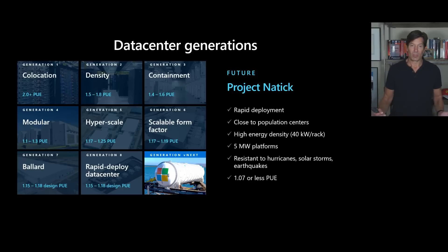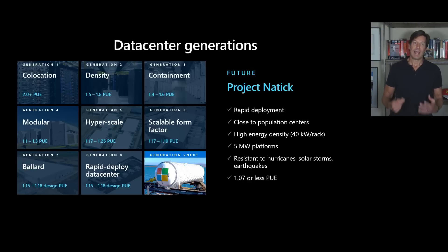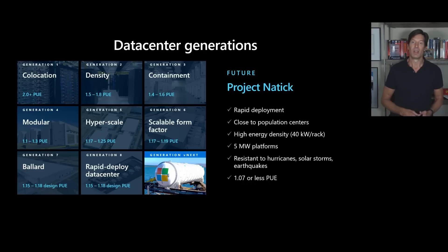First, the majority of the world's population centers are near a coastline, meaning we can deploy underwater data centers and serve just about all of the world very efficiently. Because they're on the ocean floor, they take advantage of ambient water temperature to cool, driving PUEs to levels we couldn't achieve in land-based data centers. They're also resistant to hurricanes, solar storms, and earthquakes. We can deploy them extremely quickly — you're looking at Natick V2, where we took 12 racks of Azure servers, put them in the cylinder, and dropped them a kilometer off the coast of Scotland in about 100 feet of water. From the time the cylinder was made to the time servers were on the ocean floor powered on and serving Microsoft workloads was just 30 days.